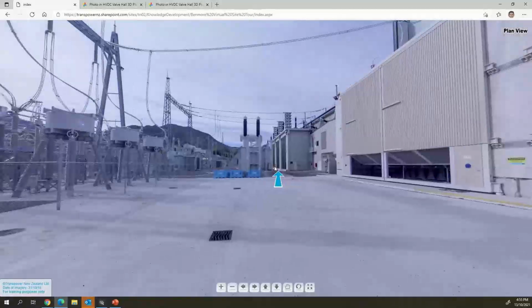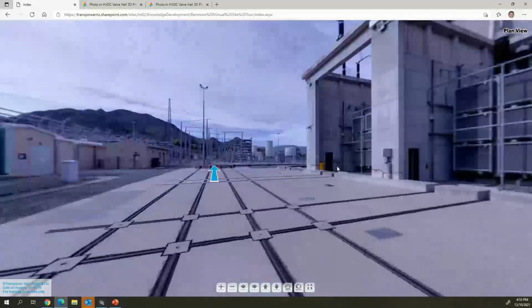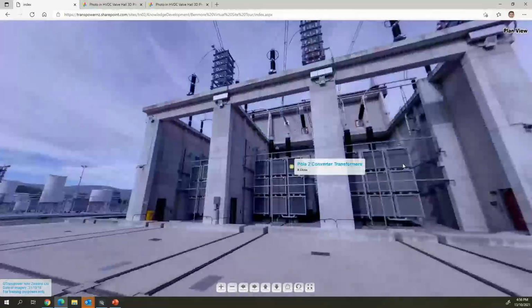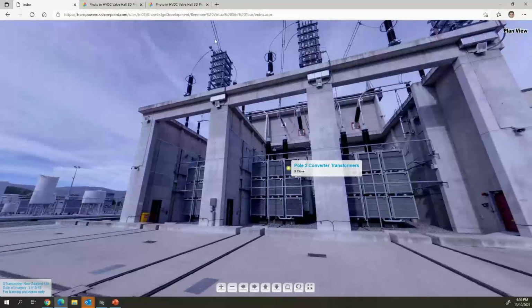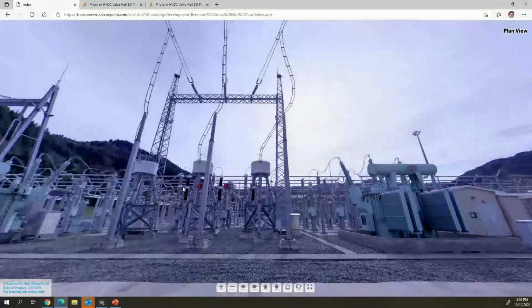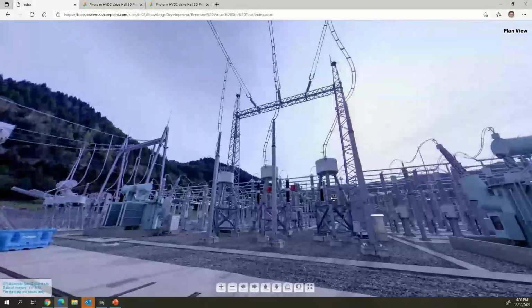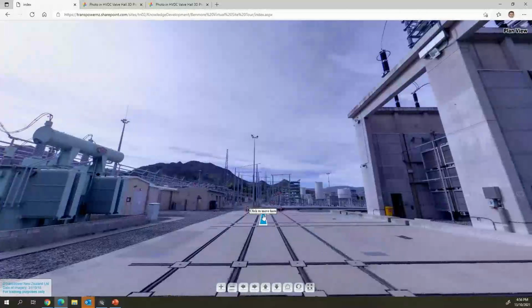I'll go over to pole 2. So these are the pole 2 converter transformers here. They've got the connections coming in on the top, 220 kV. We've got a little bit of filtering on the AC side. That's what these reactors are here for. The main circuit breaker. We'll pop over and have a look at some of the AC filters.